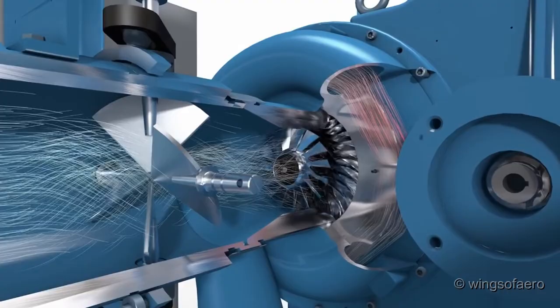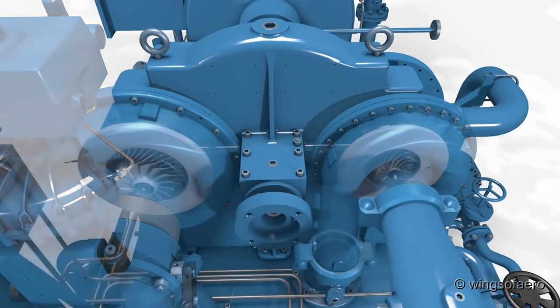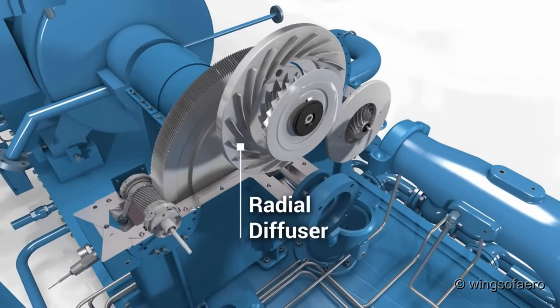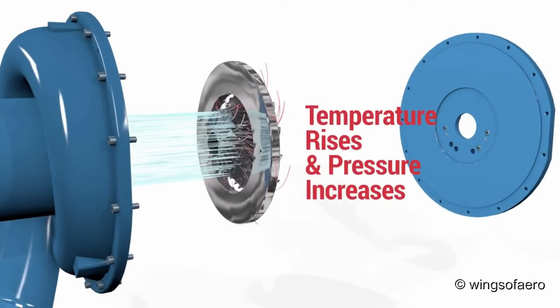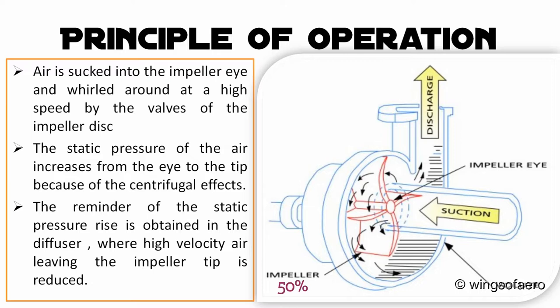It may be noted that air enters the impeller eye with a very high velocity. Friction in the diffusers will cause some losses in stagnation pressure. It is normal practice to design the compressor such that 50% of the pressure rise occurs in the impeller and the other 50% in the diffuser.